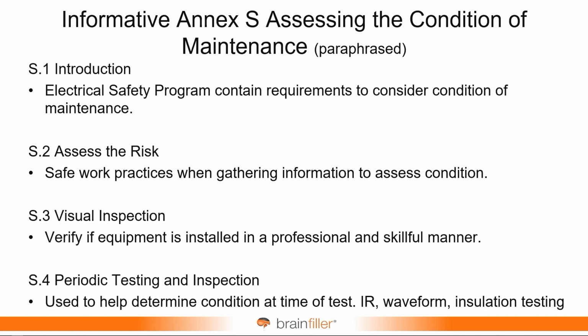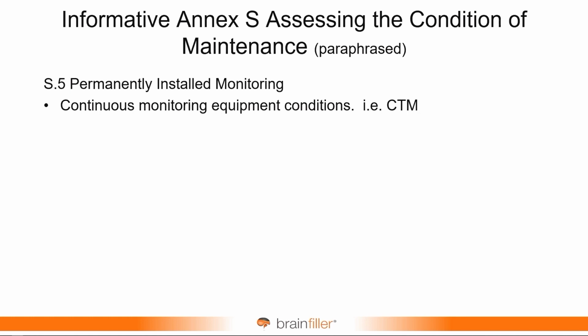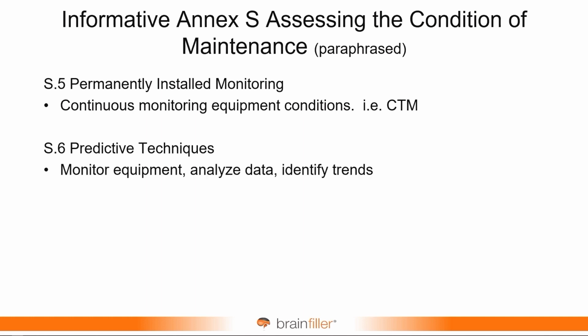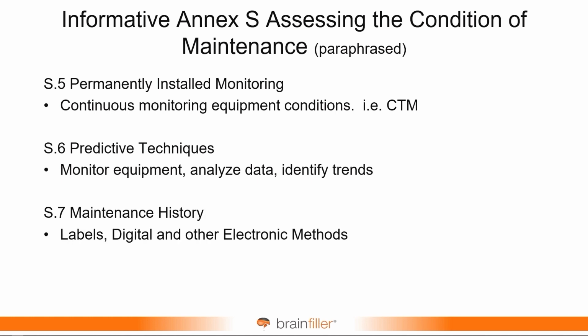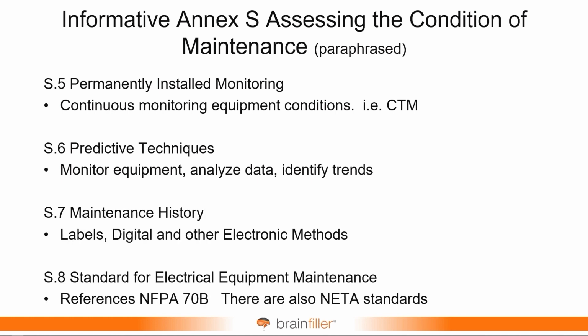S.4, periodic testing and inspection. S.5, permanently installed monitoring. And this may even include something known as CTM, continuous thermal monitoring, which is where you're continually monitoring the temperature of components instead of an occasional IR scan on a regular basis. This gives you more of a continuous thermal monitoring. S.6, predictive techniques. 7, maintenance history. And S.8, standards for electrical equipment maintenance.